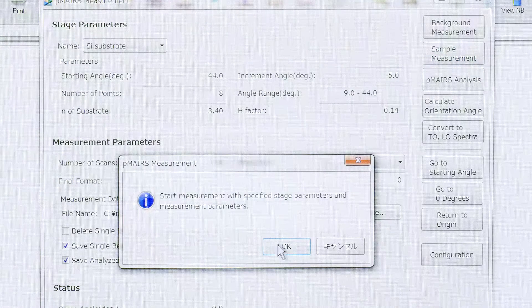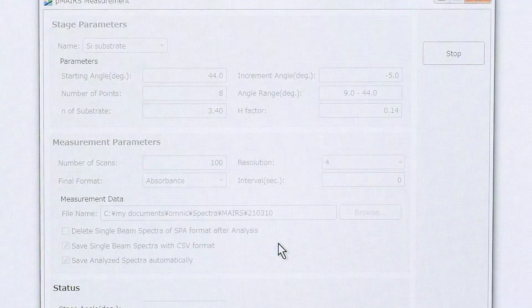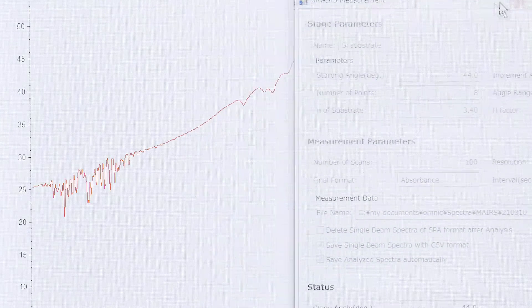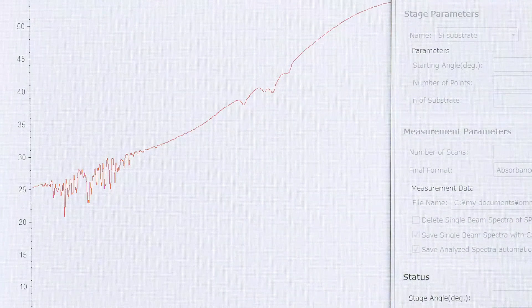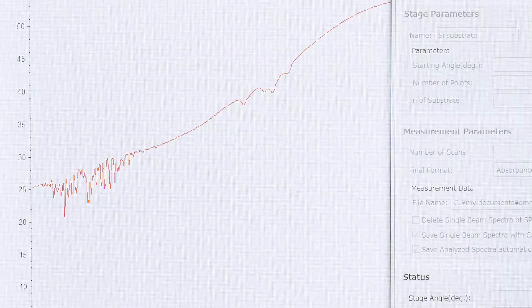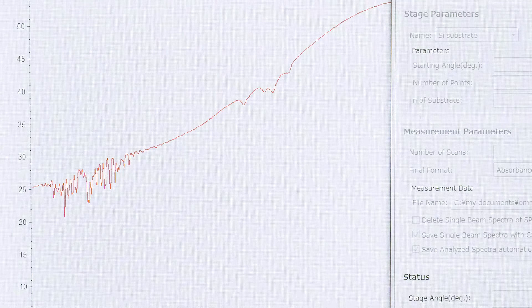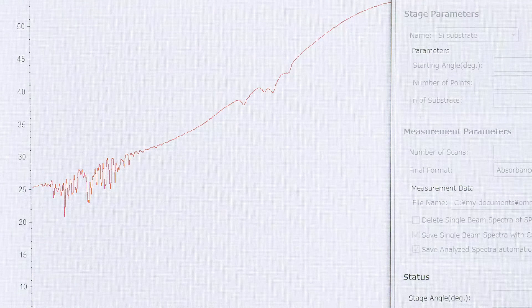After spending some time for the air purge, the sample measurements are started by pressing this button. The collection of single beam spectra at the optimal angles is performed automatically and the spectra necessary are also saved automatically. Then the same process is repeated for the background measurements.